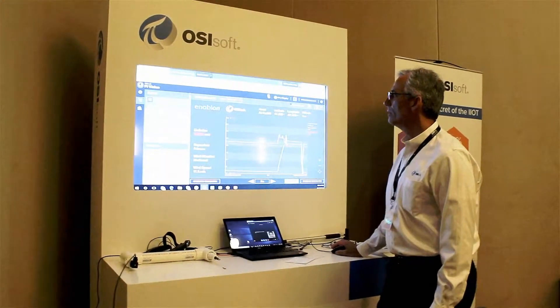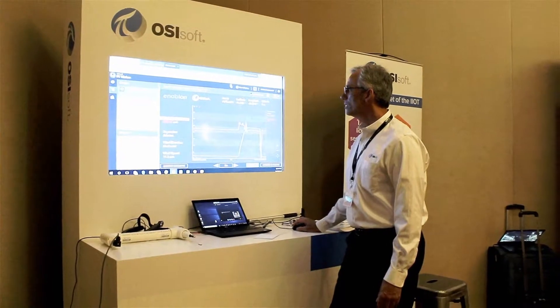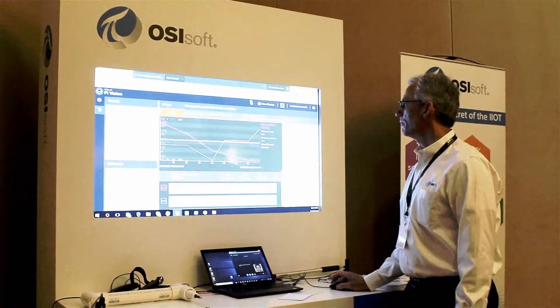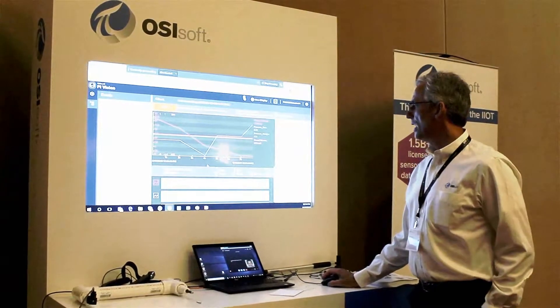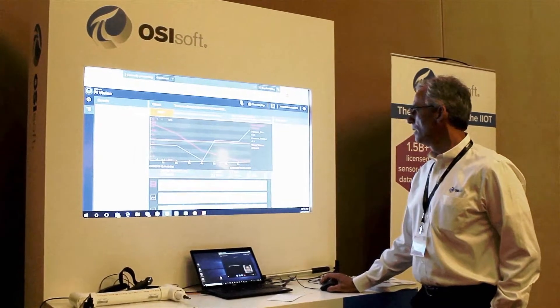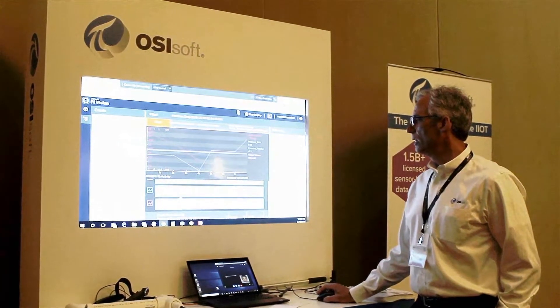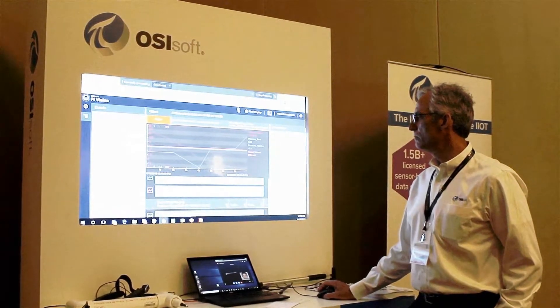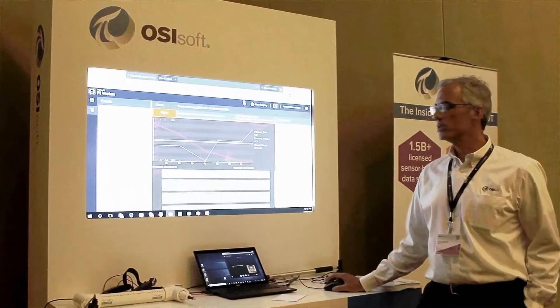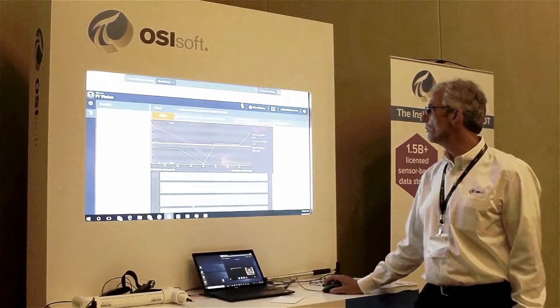Now we've created an event that says there may be some kind of risk of an air emissions event. You can see that here — pressure drop at 14 minutes, this is the one. We can view the details of that event such as the things that triggered it: the pressure itself, the rate of change of pressure, and the threshold. Also the pressure at the start and pressure at the end, which we use to calculate the estimate of emission, wind direction and so forth.